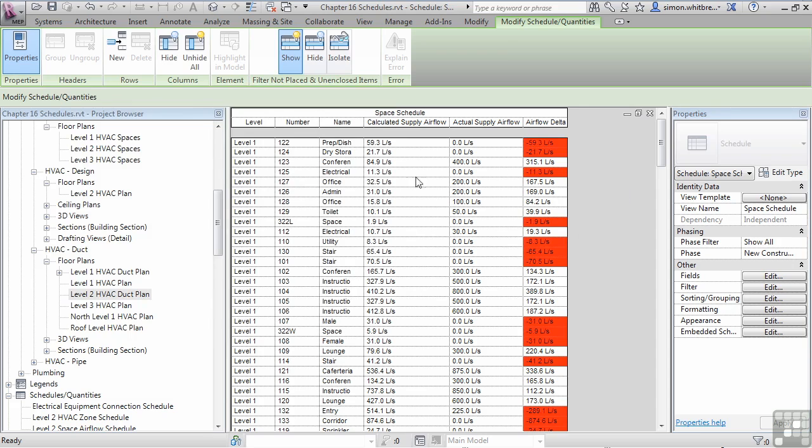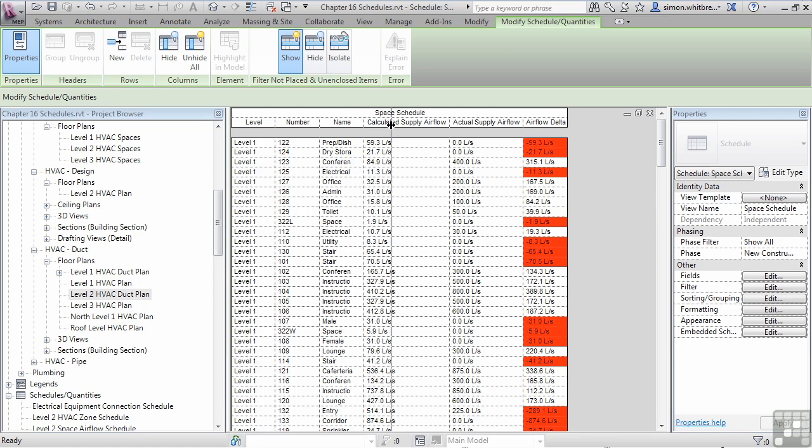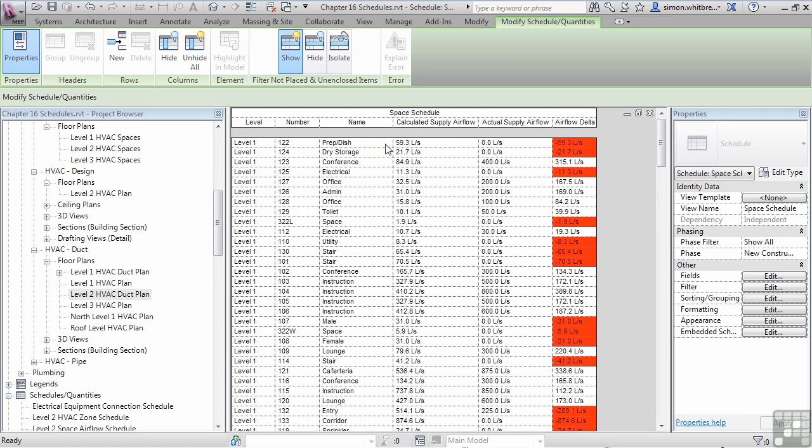And that now gives us a list of spaces where we need to go and have a look at why our air flow is less than the calculated supply air flow. Scrolling down the list of spaces, I can see that some spaces may not actually need to be heated or cooled, and we can also see spaces that have way over their air flow requirements.